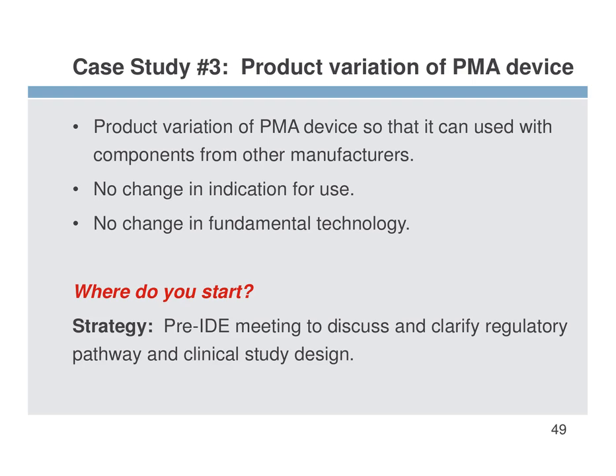So we sent in an amendment to the pre-IDE. They said, ask us new questions. And we met with them. And it was a very effective meeting because we had a really great discussion about the regulatory pathway, whether this was going to be a new PMA or whether it's going to be a panel track or a 180-day supplement. There were some questions about device compatibility, so we figured out how to deal with those. We were able to clarify the regulatory pathway and the clinical study design. So that was just an excellent time to have a meeting because we captured it soon enough.